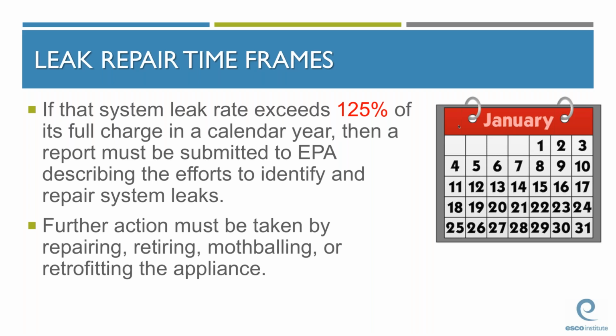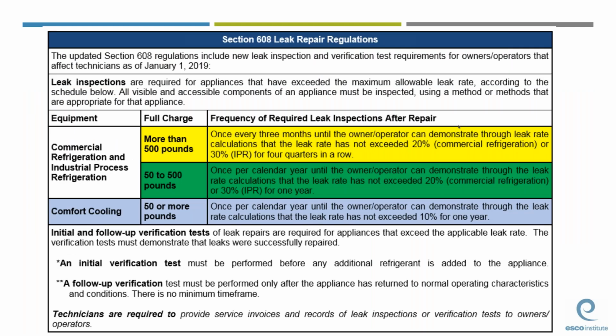So this chart that you're looking at right now summarizes the repair regulations that we've just discussed. Again, it's important to note and point out to your students that the leak repair requirements are the same for Type 2 and for Type 3. The initial leak verification test must be performed before any additional refrigerant is added to the system and before it's put back into service. The follow-up leak verification test is performed once the system has been put back into operation.